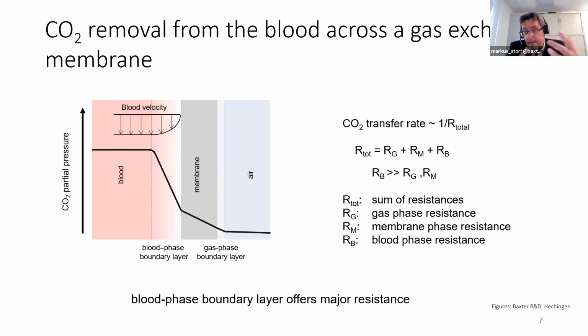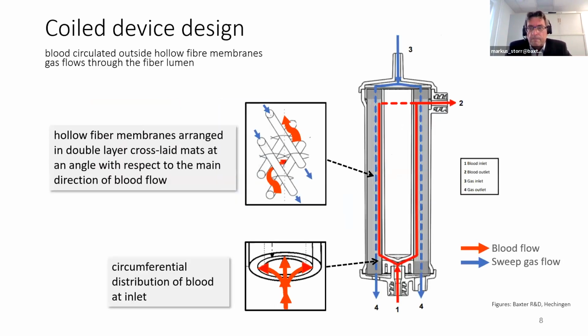So therefore, an ideal ECCO2 removal device has to focus on minimizing the thickness of the diffusional boundary layer. This can be accomplished by appropriate blood path design and blood flow conditions. And therefore, the device design and the arrangement of the membrane inside the device are of utmost importance, as you can imagine. A coiled construction design, as we see here, where blood is circulated outside hollow fiber membranes, and the membranes are arranged in double layer cross-laid mats at an angle with respect to the main direction of the blood flow, provides good mixing of the blood and thus efficient CO2 transport across the membrane wall.